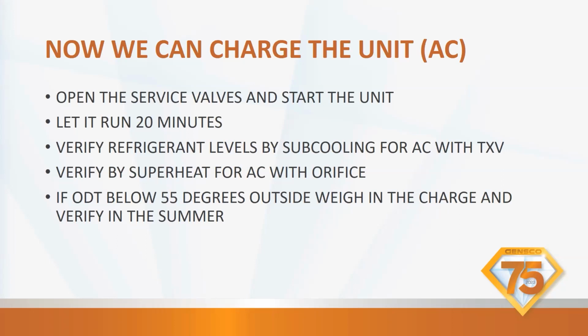The reason is that we've had units coming out of the factory that had too much charge and not enough charge. So what's easier to do, add charge or remove charge? Well, you're supposed to pull out your reclaimer and your bottle to remove charge. So that's how we got to do it. Okay. So don't add charge at the beginning.